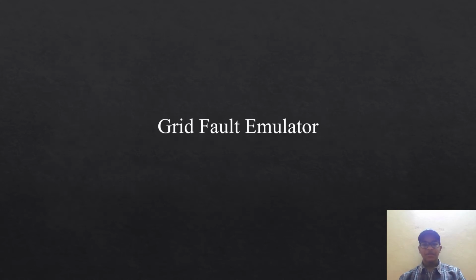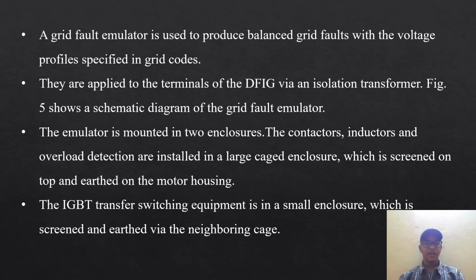Now we are going to discuss the grid fault emulator. A grid fault emulator is used to produce balanced grid faults with the voltage profile specified in the grid codes. They are applied to the terminals of the DFIG via an isolation transformer. Figure 5 shows a schematic diagram of the grid fault emulator. The emulator is mounted in two enclosures. Contactors, inductors, and overload detection are installed in the large cage enclosure, which is screened on top and earthed on the motor housing.